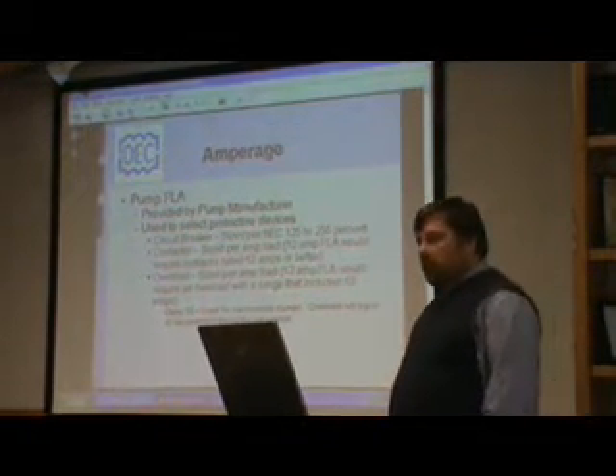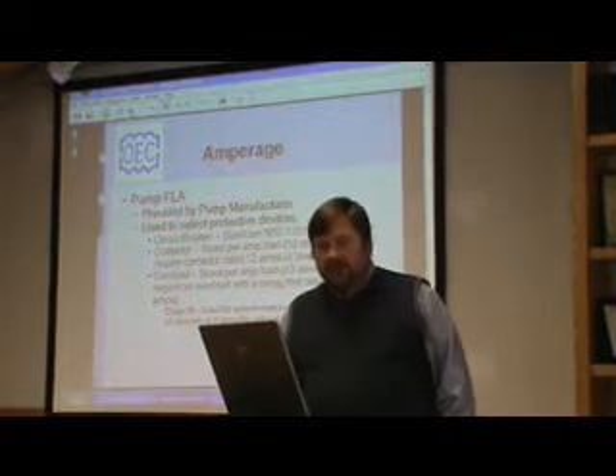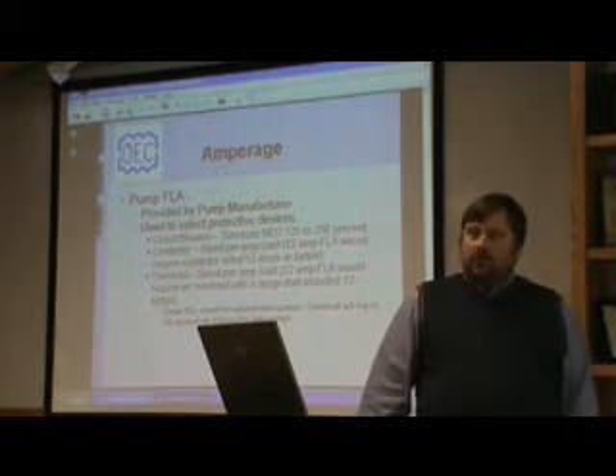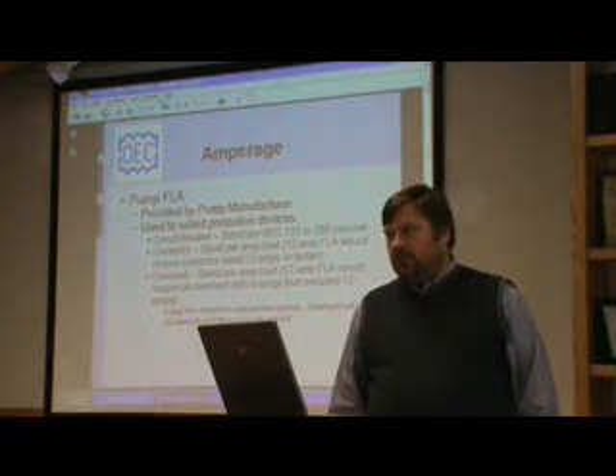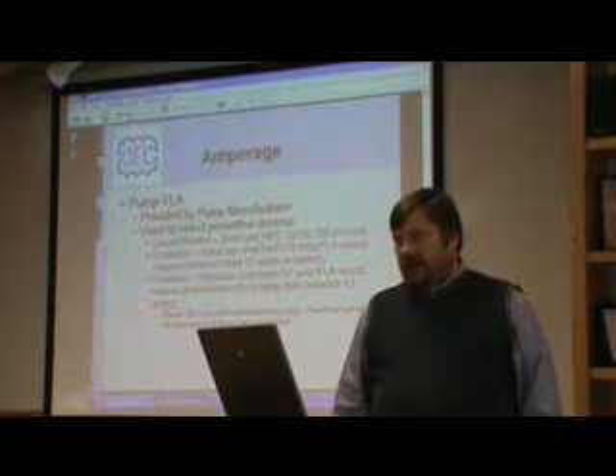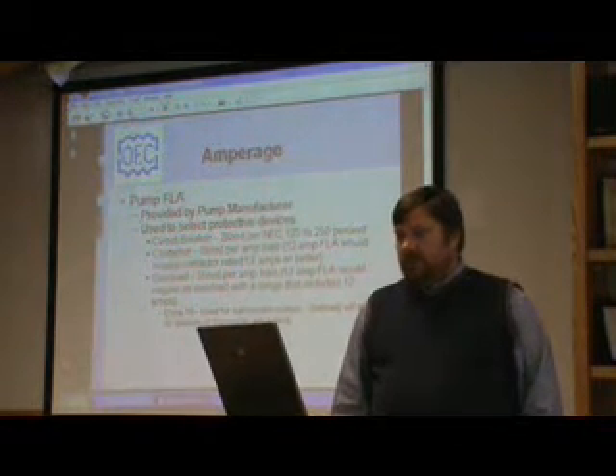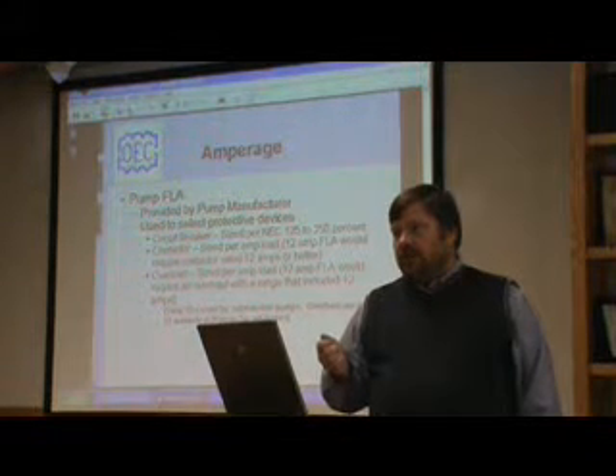All of the overloads that we use for submersible motors are what is termed a class 10. A class 10 means that the overload will trip in 10 seconds if you pull 6 times the rated current through that overload. The overload is actually the device that protects your pump. The circuit breaker is mostly there to give you a means to turn it off and to give you short circuit protection instantaneously if there's a short circuit.